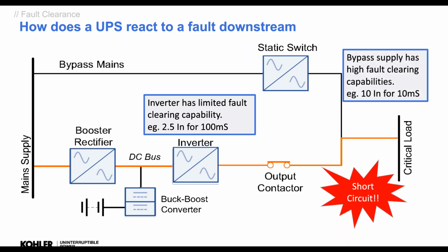Okay, the bypass though has a different clearance capability. It's effectively mains, so we'll be switched to mains. We might have 10 In for 10, 20, 40 milliseconds or so, a much higher capability. So most UPSs react very similarly. Okay, we have a capability of running an overload up to 150%, and above that it tends to treat it as a short circuit. Now the difference is, in an overload we can produce the correct voltage and supply that overload at the correct voltage for a period of time. It's limited, but it's a period of time. Whereas a short circuit means we can only supply a certain amount of current, and we limit the current by limiting the voltage. All right.